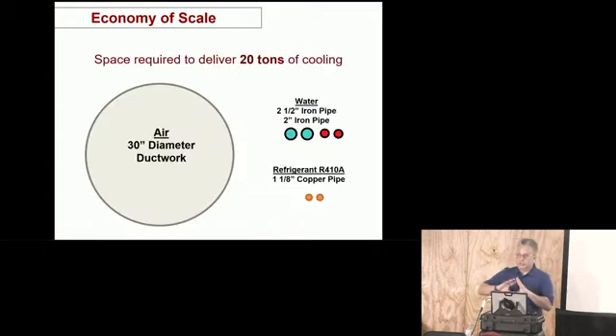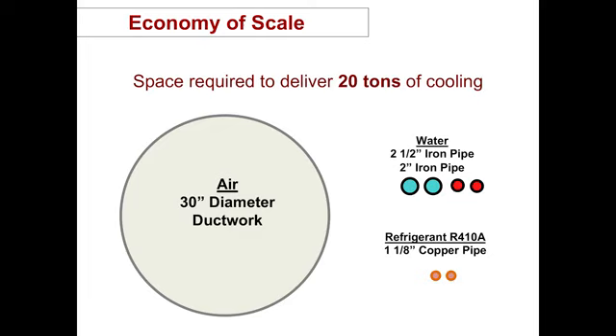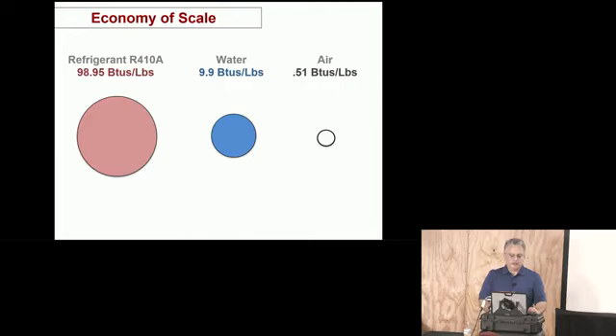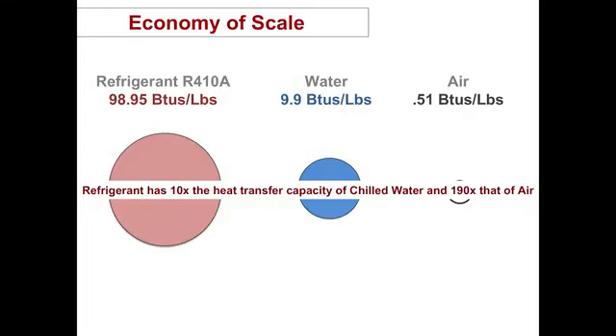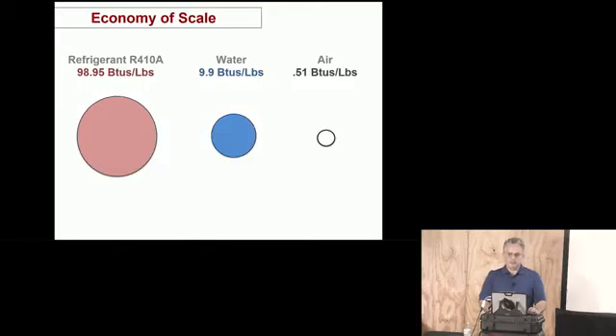But just to understand the differences between refrigerant and air and water, you can see here by this illustration how much physical space is needed to achieve the same work. So in terms of heat transfer abilities, refrigerant, R410A, has 10 times more heat transfer than chilled water, and 190 times more heat transfer than air. Is that surprising to you? No? Yeah, everybody knew that.